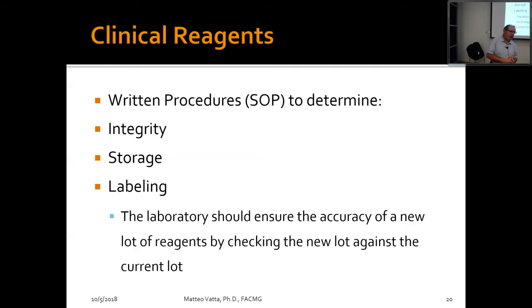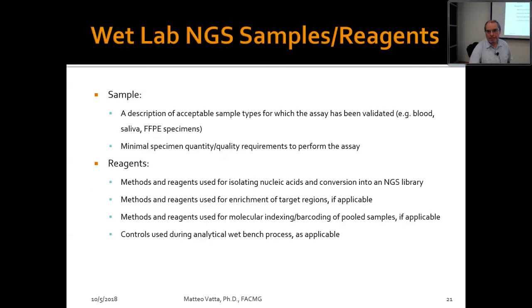So the laboratory should ensure the accuracy of all the new lots of reagents, and they have to test them with the current lot of reagents that they're using before shifting to the new lot of reagents.